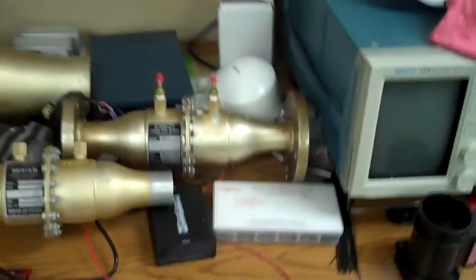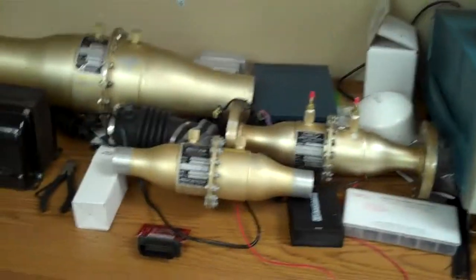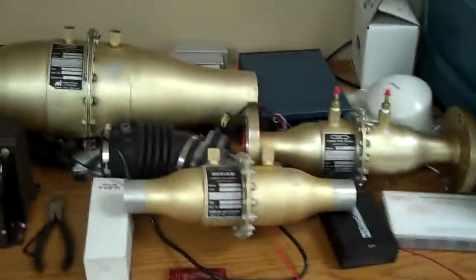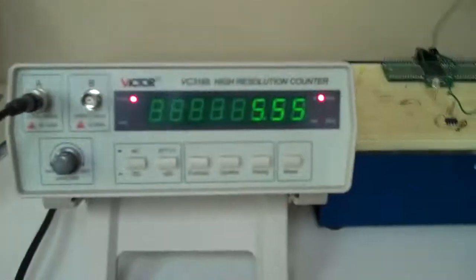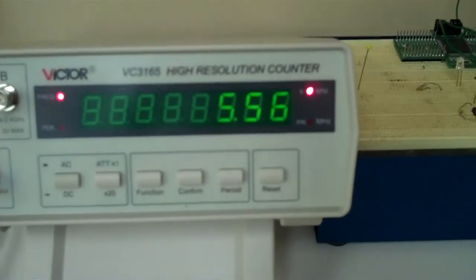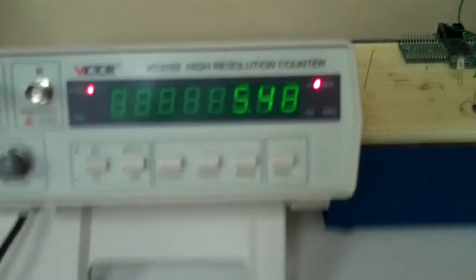This one here will go up to 400 CFM at 8 inches of water, and I've got smaller ones here as well. So the collection of laminar flow elements can swap out the range I need. And 7.12 inches of water, here is your frequency reading.